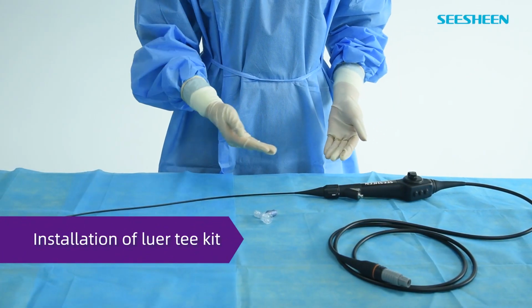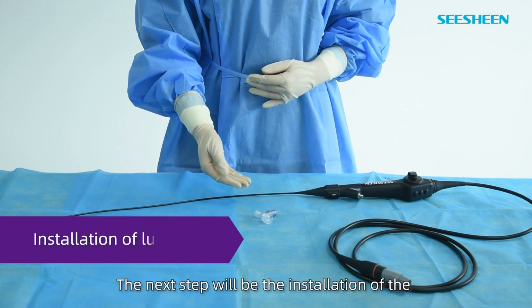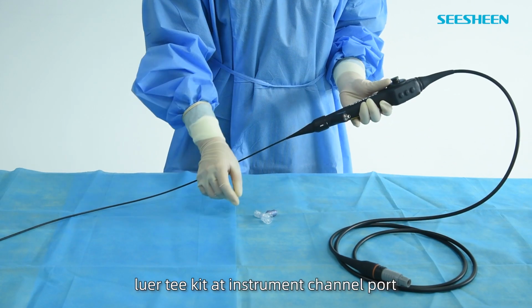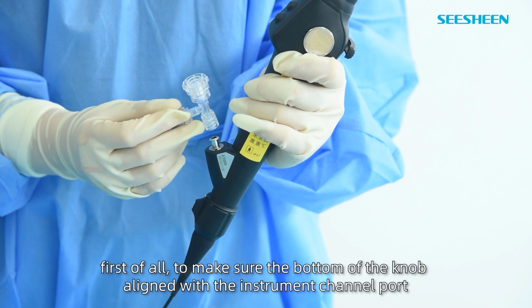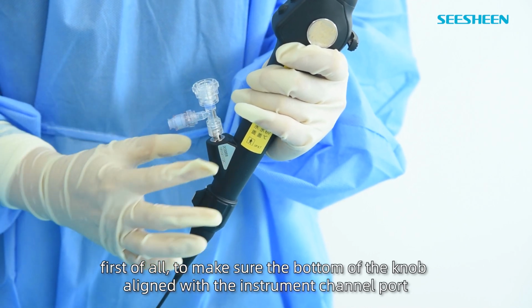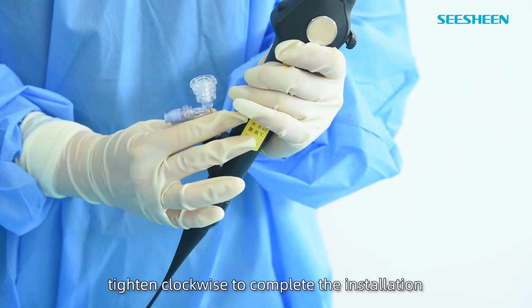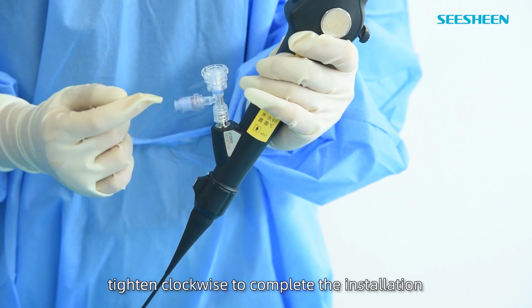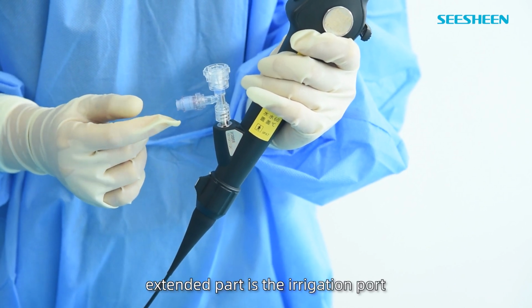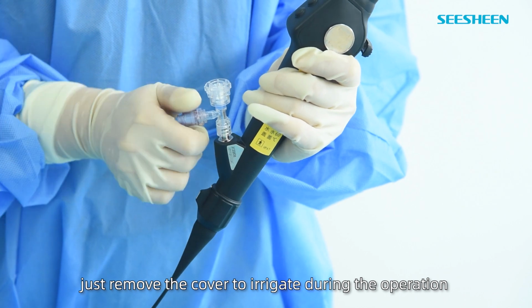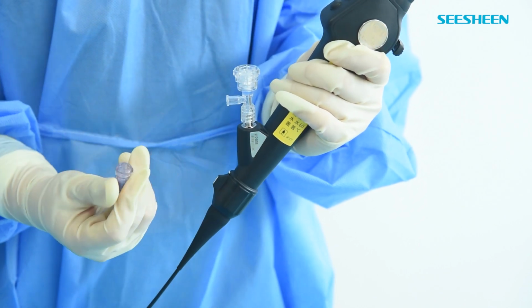Installation of luer tee kit. The next step will be the installation of the luer tee kit at instrument channel port. First of all, make sure the bottom of the knob is aligned with the instrument channel port, tighten clockwise to complete the installation. Extended part is the irrigation port. Just remove the cover to irrigate during the operation.